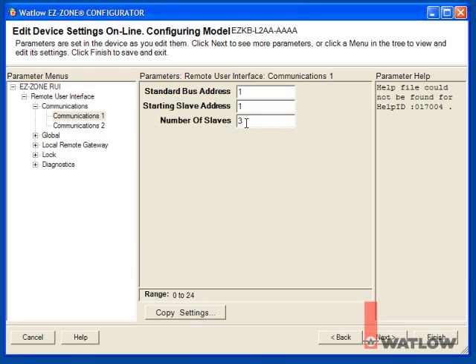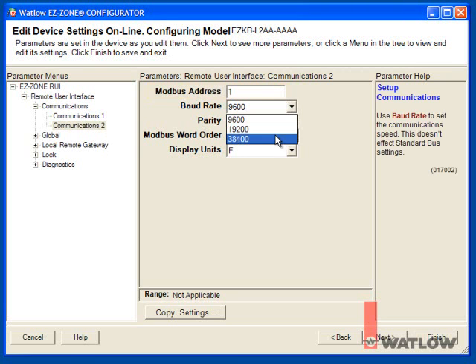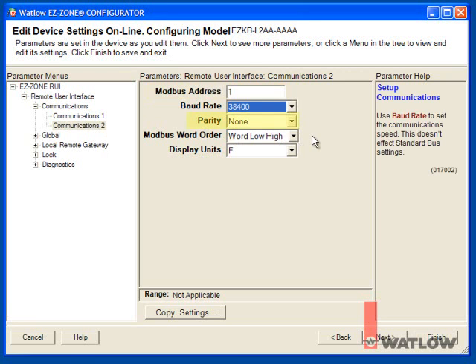To set up Modbus on the other communications port, choose the Communications 2 menu. Modbus address determines the network address of the gateway. This must match the setting we make later in the OIT. The default setting 1 is best. Set the Baud Rate, we'll use 38,400. We'll use the Parity set to None, and the Modbus Word Order set to Word Low High. Set the Display Units to the Temperature Scale you want.